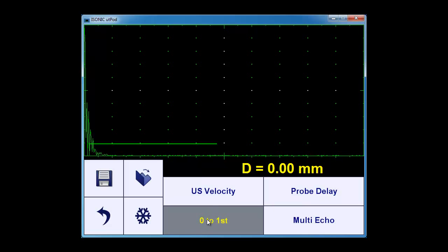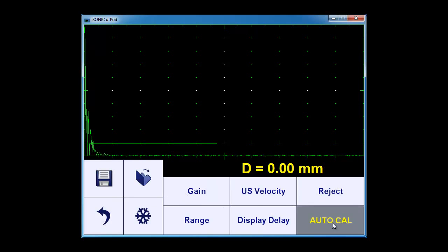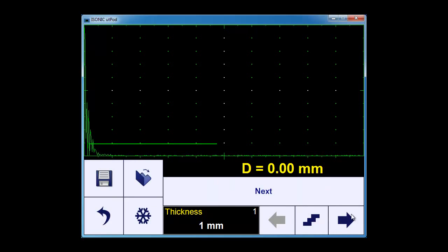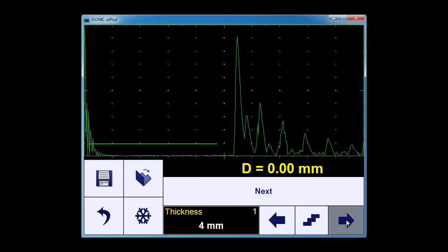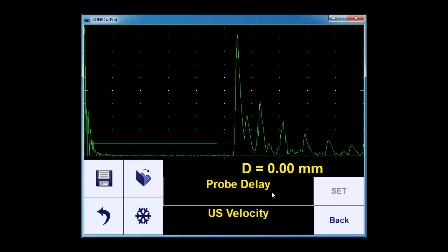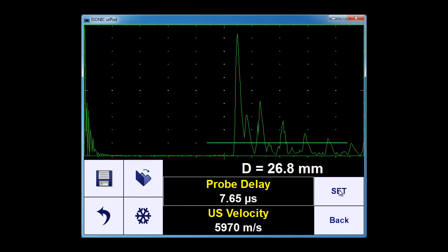First of all, let's have a look at the zero to first echo measurement. I go to basic, auto calibration. Now I couple my probe to the test piece, to the calibration block. I have a 4 mm calibration block here, so I put the thickness on 4 mm, click next.